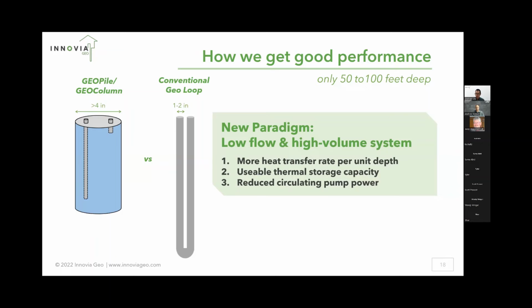And so a question that I'm sure is on your minds is, how do we get good performance in a geothermal system that's only going 50 to 100 feet deep, as opposed to these systems that have to go hundreds of feet deep? And so there's a couple of factors here, but it boils down to the principle of low flow and a high volume system that we've developed here. And so in a conventional geothermal system with the small pipes about 1 to 2 inches in diameter, the principle is you've got to push that fluid through quickly so that it encourages mixing of that fluid to exchange that heat with the ground. So our system is designed a little bit differently, where we have a much larger pipe, greater than 4 inches in diameter, and our design principle is to actually trickle that fluid into that larger pipe so that it spends as long as possible in the ground to exchange heat that way, rather than pushing it through and encouraging that mixing.